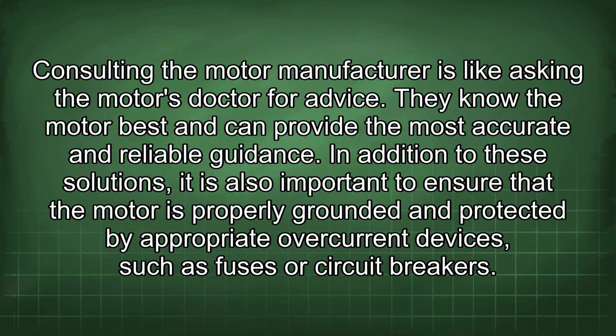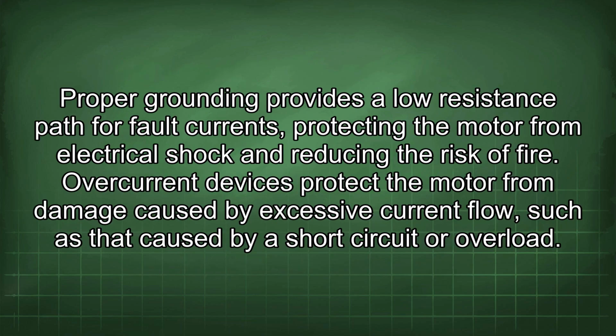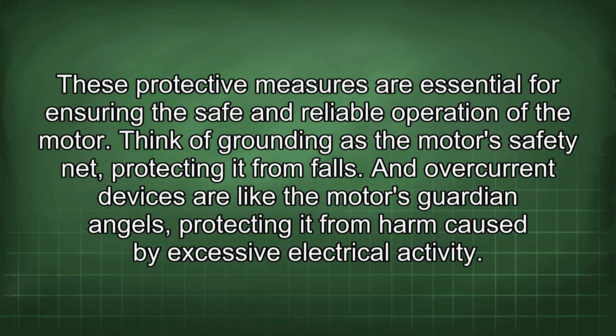In addition to these solutions, it is also important to ensure that the motor is properly grounded and protected by appropriate overcurrent devices such as fuses or circuit breakers. Proper grounding provides a low resistance path for fault currents, protecting the motor from electrical shock and reducing the risk of fire. Overcurrent devices protect the motor from damage caused by excessive current flow, such as that caused by a short circuit or overload. These protective measures are essential for ensuring the safe and reliable operation of the motor. Think of grounding as the motor's safety net, protecting it from falls. And overcurrent devices are like the motor's guardian angels, protecting it from harm caused by excessive electrical activity.